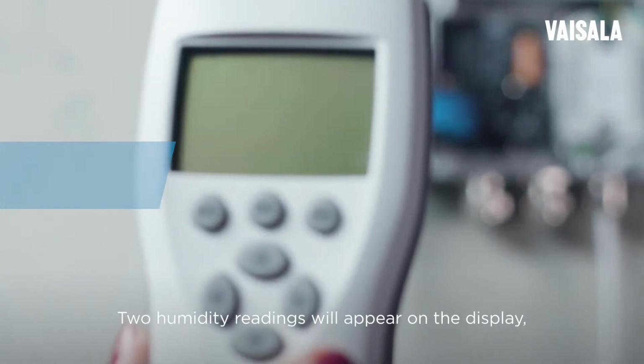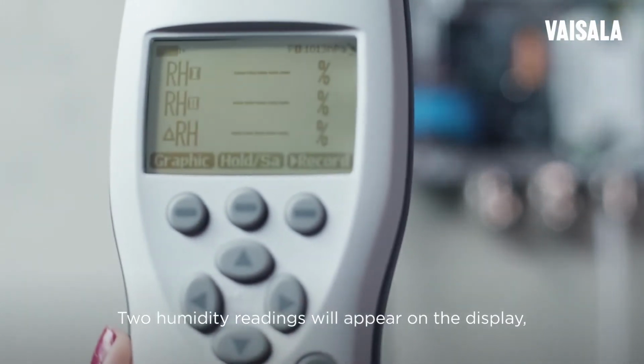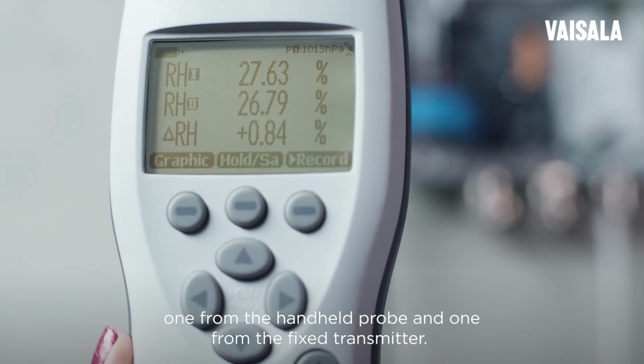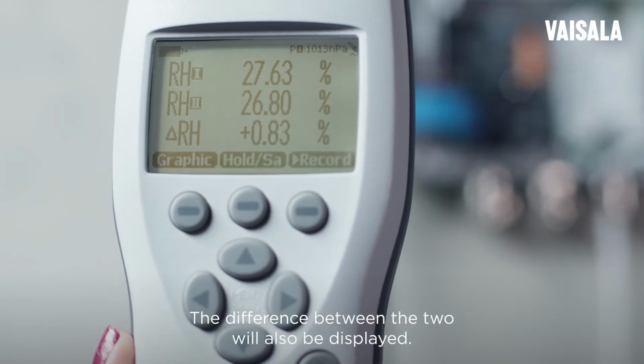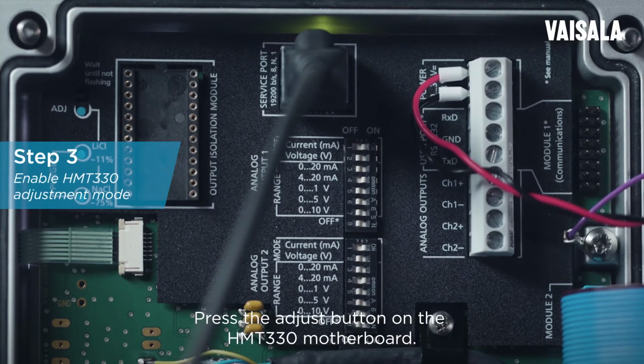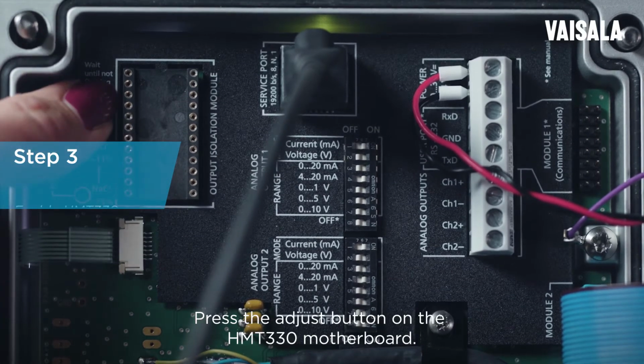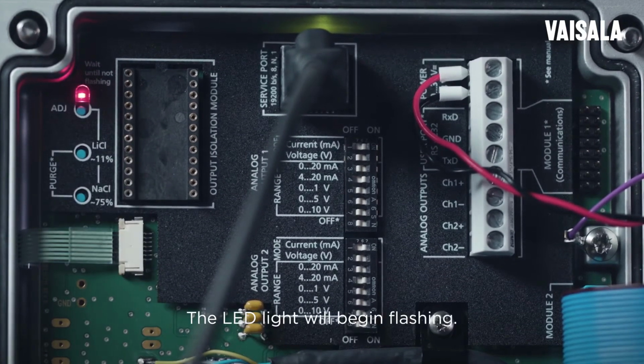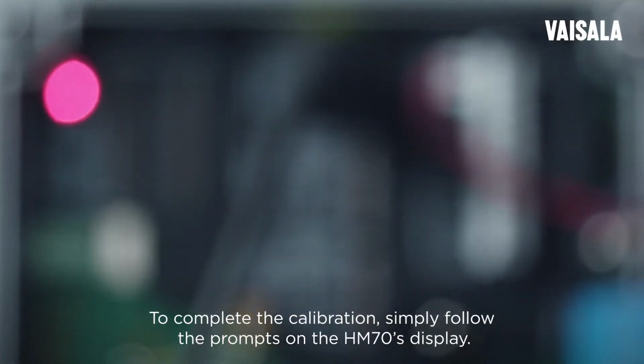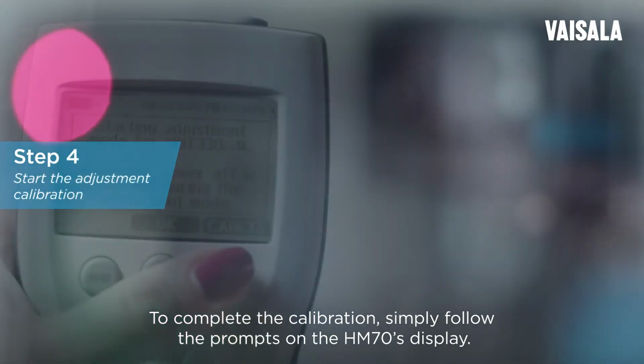Next, power on the HM70 meter. 2 humidity readings will appear on the display, one from the handheld probe and one from the fixed transmitter. The difference between the two will also be displayed. Press the Adjust button on the HMT330 motherboard. The LED light will begin flashing. To complete the calibration, simply follow the prompts on the HM70's display.